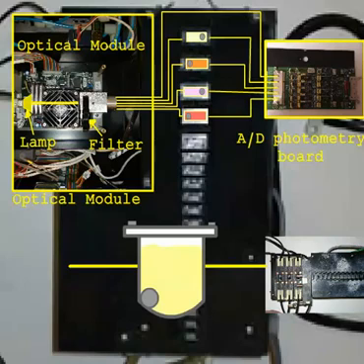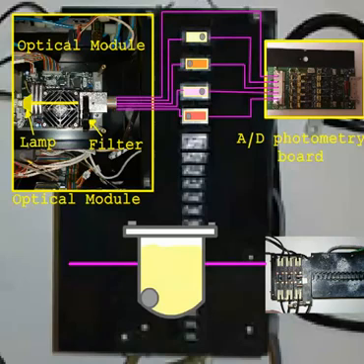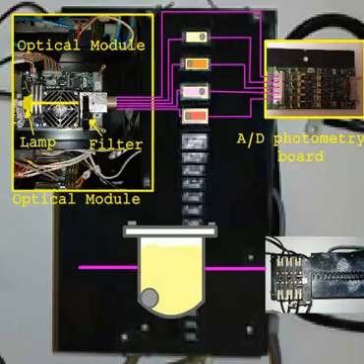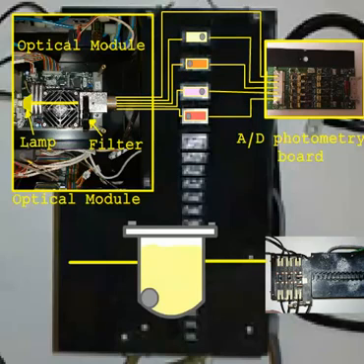The light goes through the filter, goes through four optical fibers, one to each channel on the measurement block, and a fifth fiber, which is the reference fiber, which goes directly to the photometric measurement board.